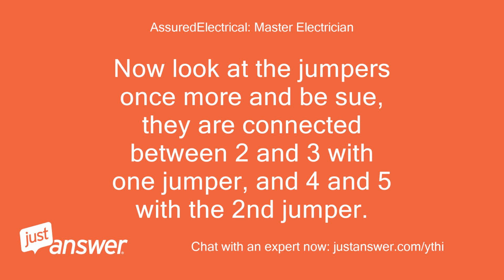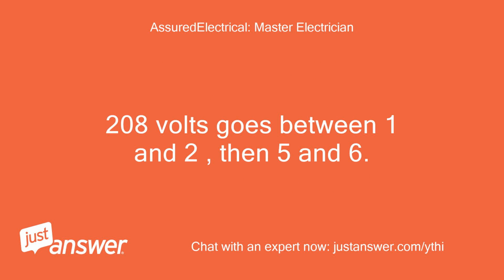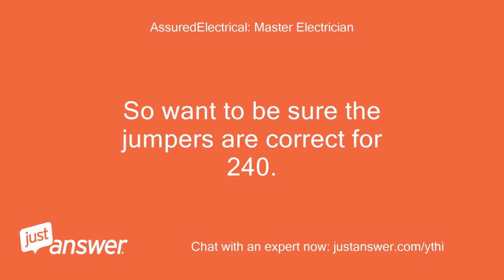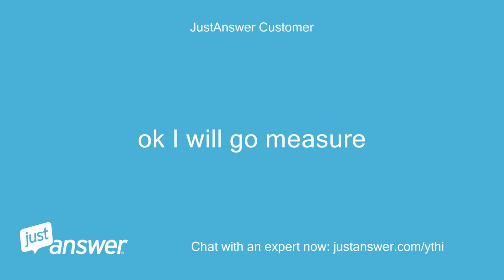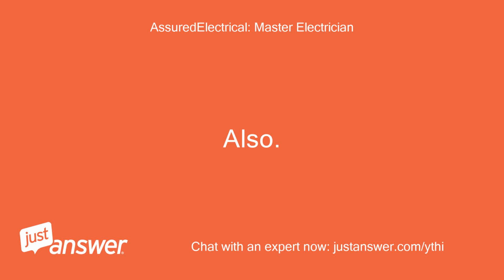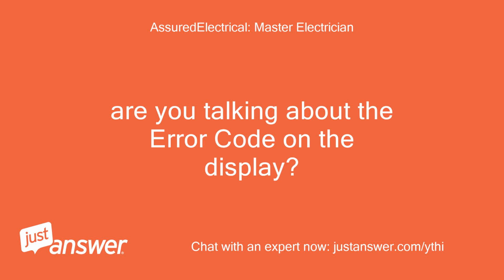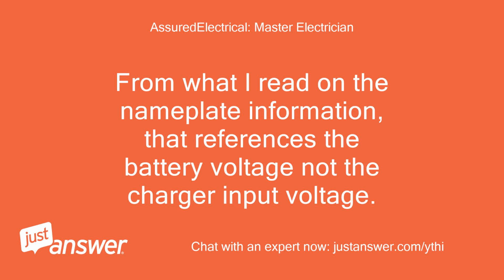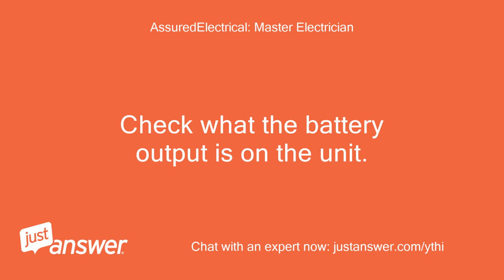Now look at the jumpers once more and be sure. They are connected between 2 and 3 with one jumper and 4 and 5 with the second jumper. 208 volts goes between 1 and 2, then 5 and 6. So want to be sure the jumpers are correct for 240. Okay, I will go measure. Also, are you talking about the error code on the display? From what I read on the nameplate information, that references the battery voltage, not the charger input voltage. Check what the battery output is on the unit.